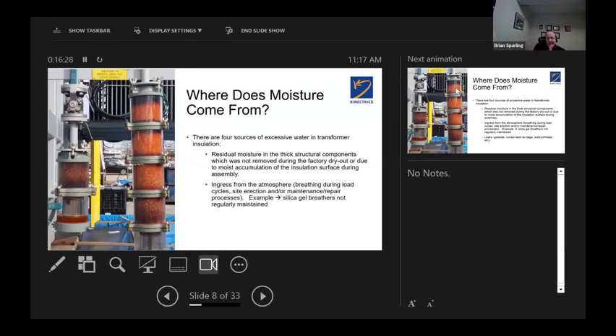Moisture from the atmosphere, breathing, open breathers during load cycles. And that's why you may have things like this silica gel arrangement to keep the air dry as much as possible from the air in the conservator exposed to the ambient, to try to keep the moisture out. But this is an item that needs to be regularly maintained and watched as to when to go about replacing that silica gel.